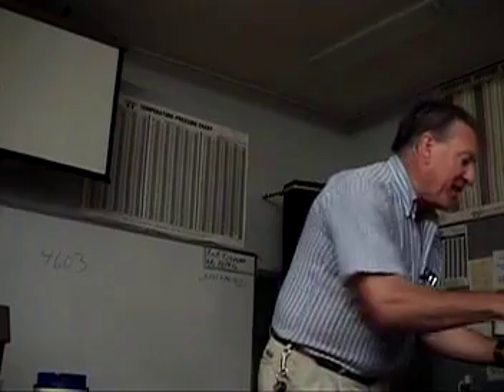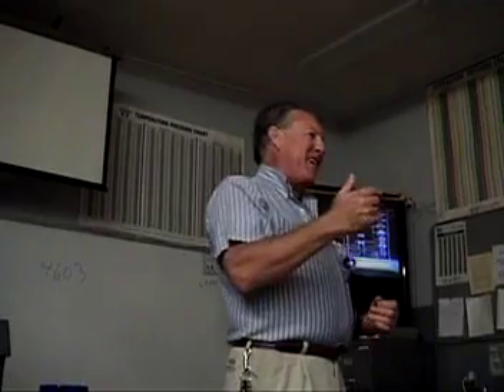This unit that I have back here, that fan has been replaced. The schematic that goes with that unit back there is not correct. And you'll run into this all the time. You go up to a unit, you look at the schematic, it's got the way the fan's wired. It's a new fan. It's wired different. You've got to look at the fan, and there's going to be a little schematic on the fan, and you've got to make that schematic work on your old schematic. That's why I did that. They don't match. I didn't do it on purpose. Somebody burned out the fan. I put that one in. But it's good practice because you're going to run into this a lot, where a component's been put in, it's wired different, and it's got its own little schematic on it, like that one has.